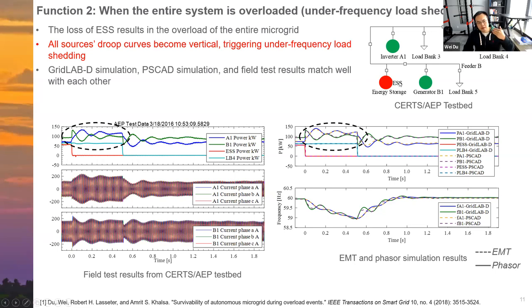So the frequency keeps dropping during this overload event. And then we have a frequency relay installed at load bank 4. This frequency relay detects this under frequency event and trips load bank 4, and the system survives this overload event. So the key message is that when all the sources in the microgrid are overloaded because of a loss of generation event, the droop curve of all grid forming inverter sources becomes vertical because of that Pmax controller. And then that can help trigger the under frequency load shedding in this microgrid.